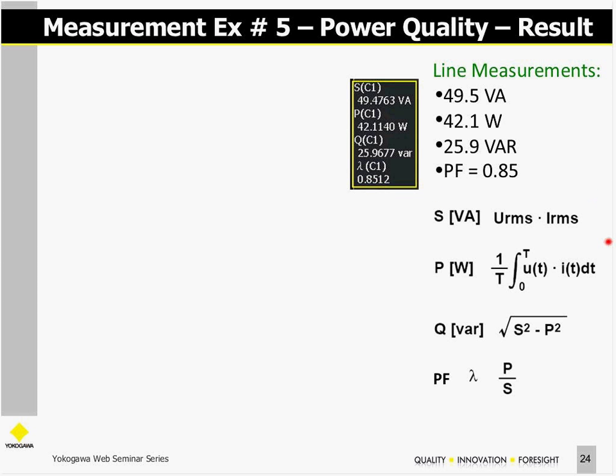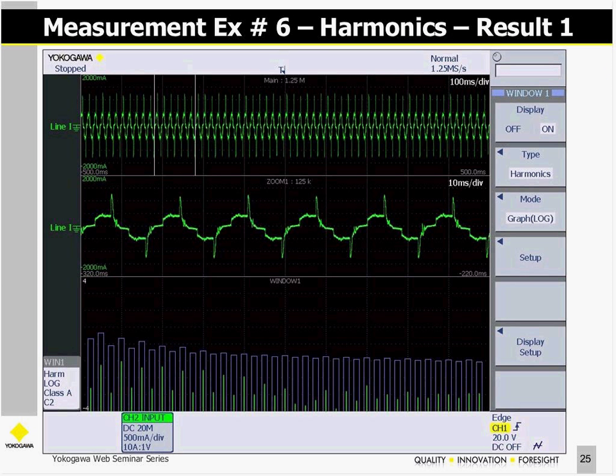Here are the equations. These are all IEEE approved measurement methodology, including power factor. The true definition of power factor is the power in watts, P, divided by S in volt amps. There's no phase measurement or phase angle measured in this calculation; it's simply P divided by S.